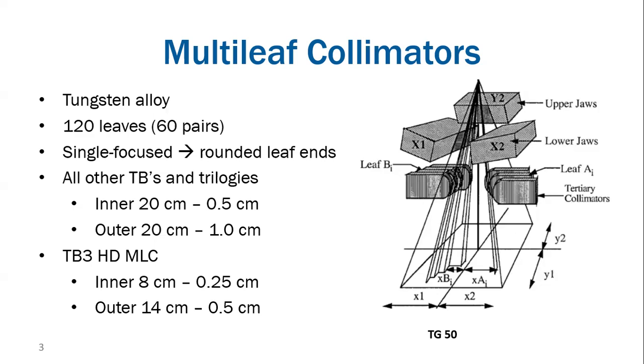However, if you are starting a stereotactic radiotherapy program, you'll probably want a linear accelerator with high definition MLCs. And these have a smaller MLC carriage. However, the inner 8 centimeters are only a quarter of a centimeter in thickness. So you're able to get more of a conformal shape in your target. And then the outer 14 centimeters are a half of a centimeter.